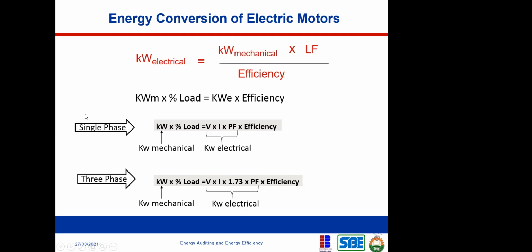For a single phase motor, this is the formula you're going to use: kilowatt mechanical times the percentage loading. If you're not given the percentage loading, just assume it's 100% load, just assume 1. But if you're told that this motor is loaded at 50% of its capacity, or 30%, then you have to put that here.